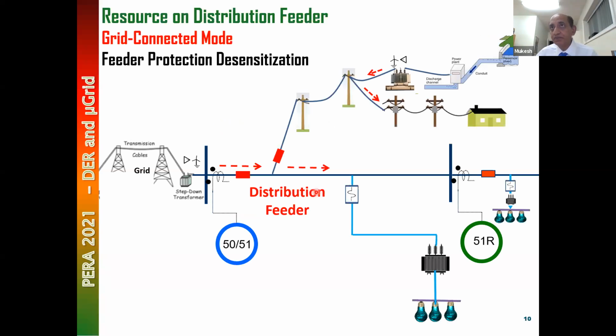We'll talk about grounding. So this is a traditional distribution system, very similar to what I showed before. High voltage or sub-transmission system, transformer, step down, then you have a 25 kV or 12 kV system, long overhead feeder, maybe going to a single phase transformer, this may be a single phase pole mounted transformer, protected by a fuse. Now you will have protection right in the substation. You'll have substation protection, which is an overcurrent relay, inverse instantaneous and inverse time overcurrent relay connected to a CT, and it will trip this circuit breaker. This is all in the substation.